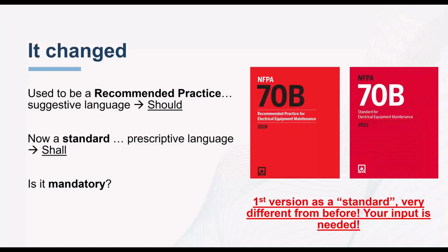The document has been around for quite a few years, but it's always been a guide. And whatever level of attention it has received in the past, the intent of the NFPA in changing it to a standard is to increase that level and really bring it on par with the National Electrical Code and 70E. So it is now a standard. It is prescriptive language. It does say thou shalt do that, not that you should, you could, you might. No, it flat out says you shall do that.